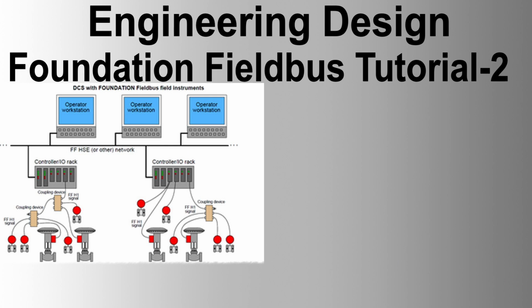FMS objects. Applications in a VFD are shown to other applications on the network using an object model, which consists of attributes, behavior, and access methods. Examples of objects include function blocks, alarms, and schedules. An object is identified with a number called index, which is unique within the VFD. Additional information to describe an object is called the Object Dictionary, OD, which is an assembly of information called object descriptions to explain the objects.